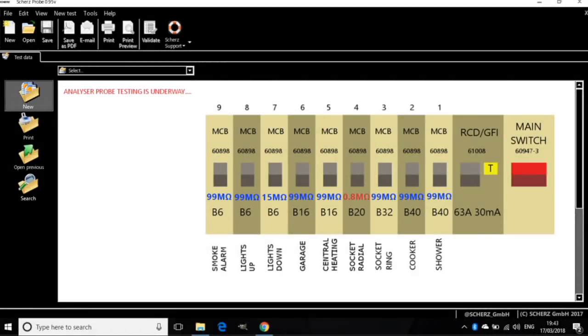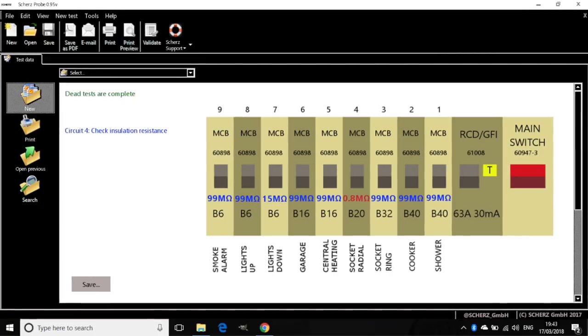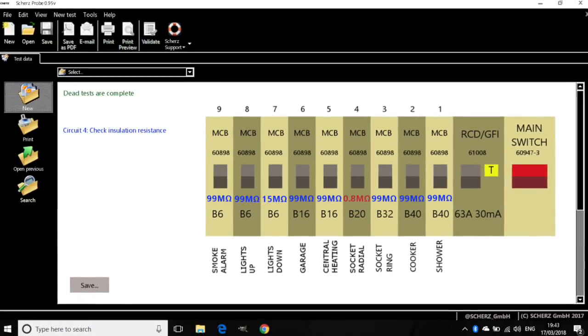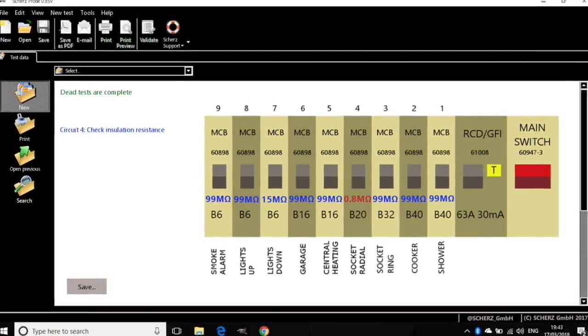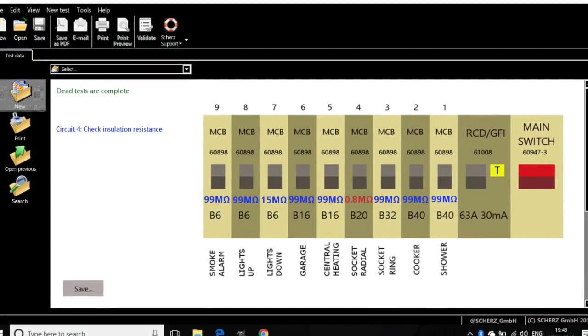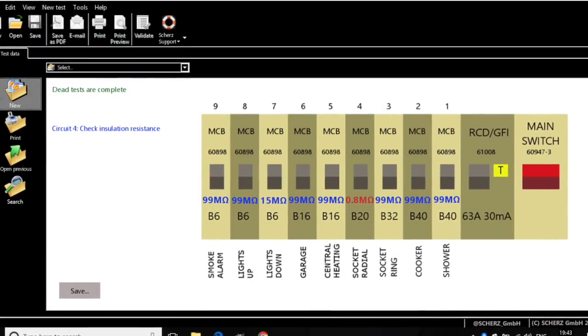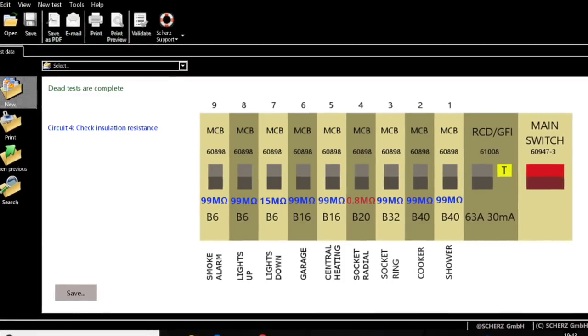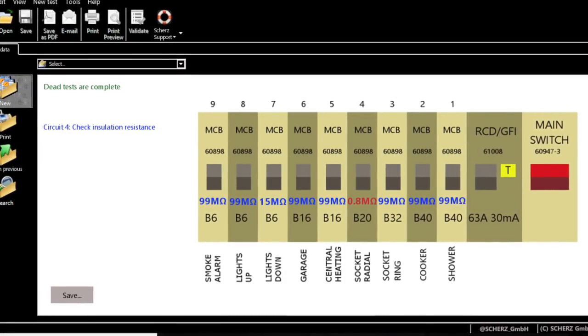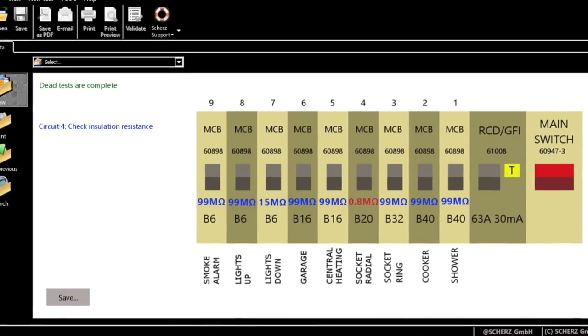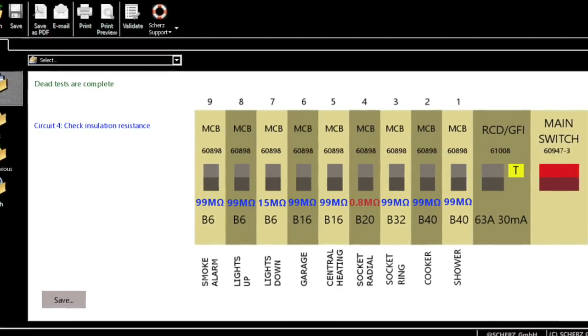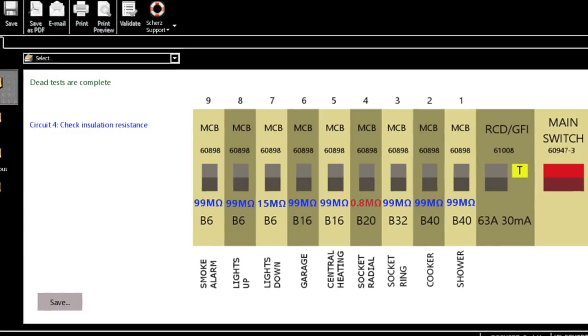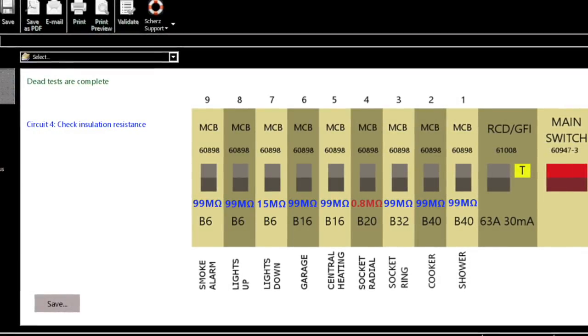The analyser probe can perform an IR test at 250 or 500 volts thanks to a micro step-up coil built into it. Results come back in up to 99 megaohm, which is a lower full-scale deflection than most IR testers on the market, but plenty high enough to satisfy regulatory testing requirements. It auto shorts line to neutral internally, so cannot IR test between live conductors, but it does test both live conductors of each circuit with respect to earth. Again, frequency separated probing allows it to test each circuit individually but simultaneously without disconnecting any wiring.